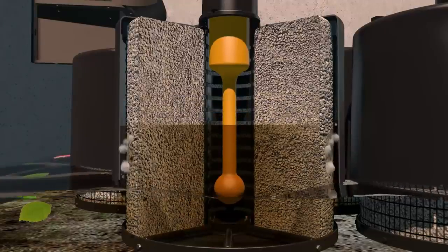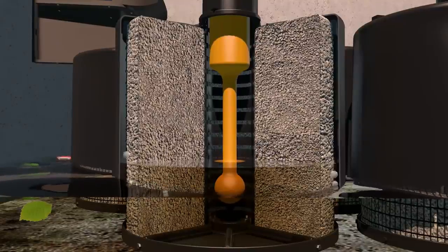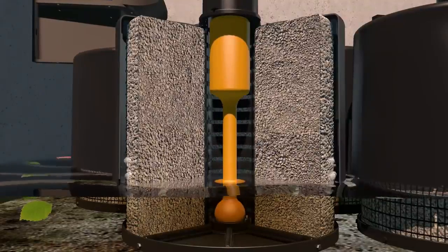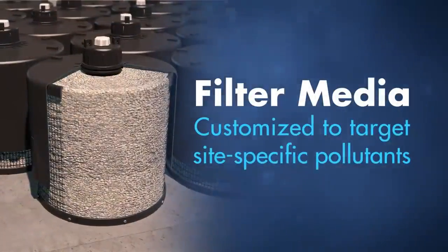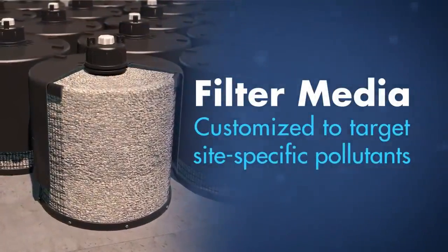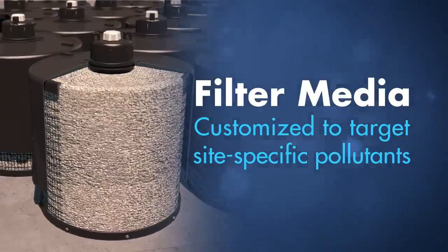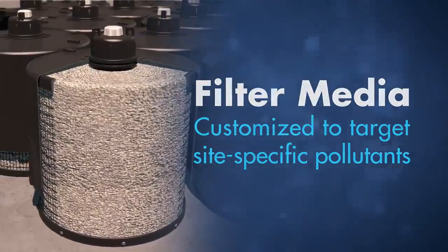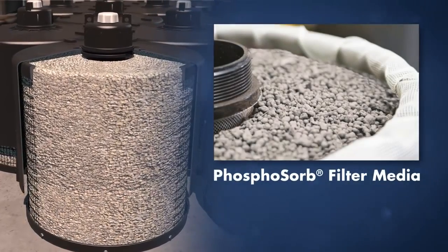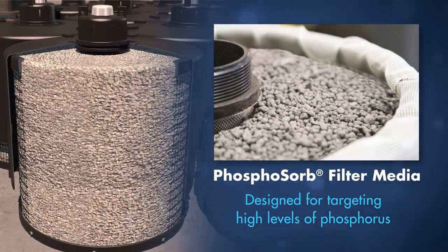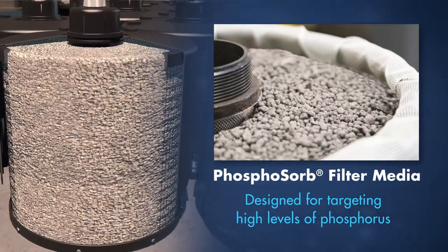This patented surface cleaning mechanism helps restore the permeability of the filter surface during drain down and between storm events. The filter media in the storm filter cartridges can be customized to target site-specific pollutants. For example, in applications targeting phosphorous, Contech developed Phosphosorb — a unique filter media designed specifically for applications targeting high levels of phosphorous removal.